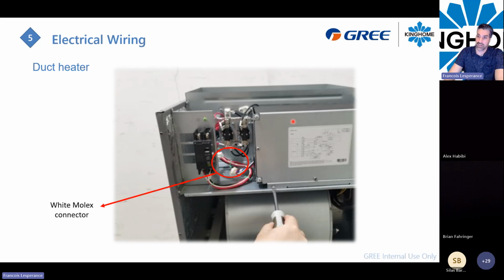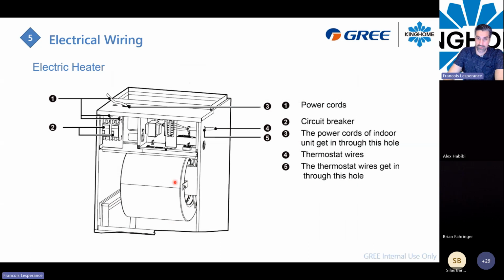And so you reinstall the electrical box right here, and after that you will have this white Molex plug right here. This connector needs to be connected, so you will bring the power directly to the breaker right here. You don't have to bring the power in the electrical box anymore. It will just be applied to the breaker right here. And by connecting this white connector right here, you will apply power automatically on the board and for the blower and all the stuff. So this is just another diagram right here. So you can use the knockout hole right here to bring the power to your breaker and all the stuff. The low voltage connection will be at the same place here. So you have your low voltage connection directly on the terminal strip right here.